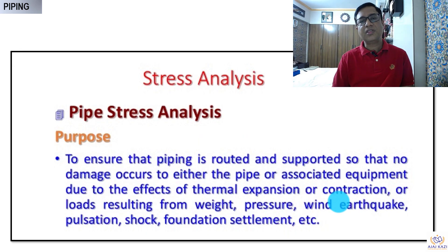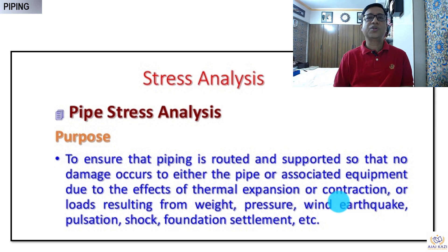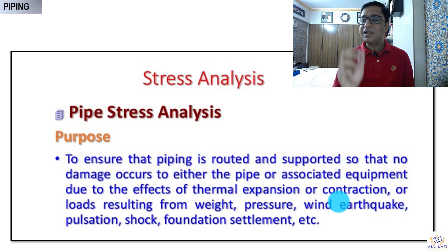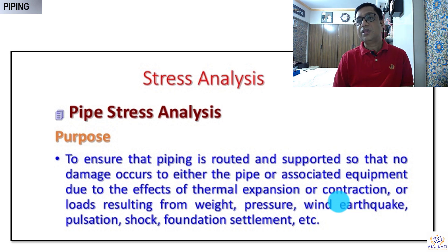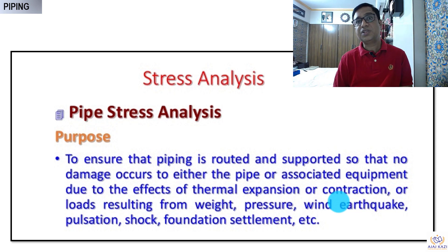Stress analysis is another important subject. Generally, in specific dimensions, support spacing is between 2 and 3 meters depending on the specification. The best way is to have a stress analysis done — there are software tools available that tell you exactly where the stress is and where the right support is needed. Otherwise, if you go only by specification, the supports may not match the actual stress.